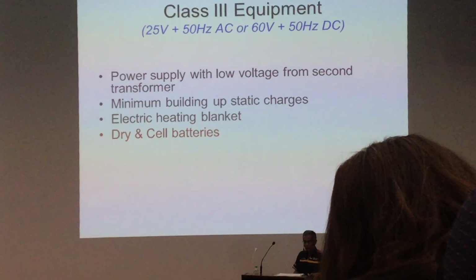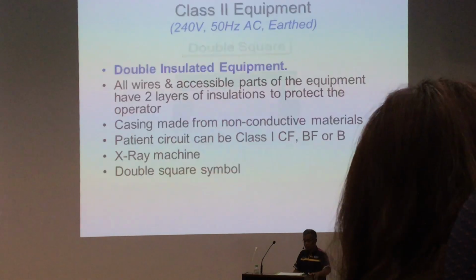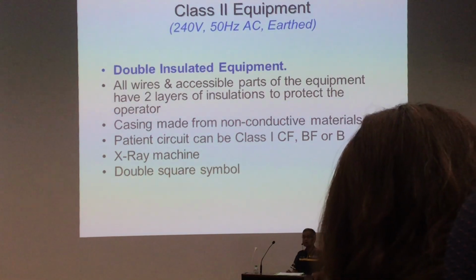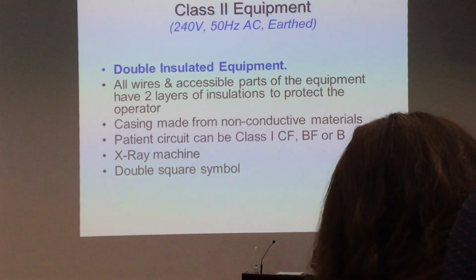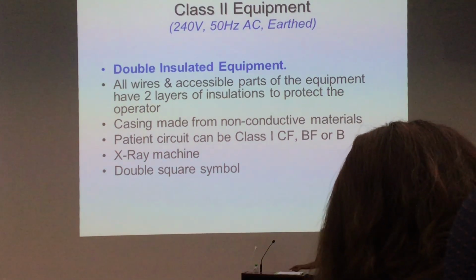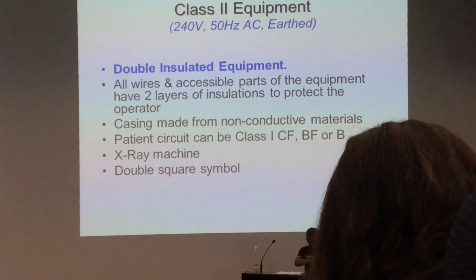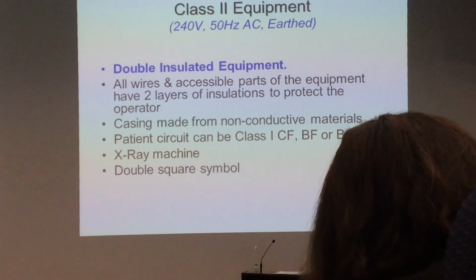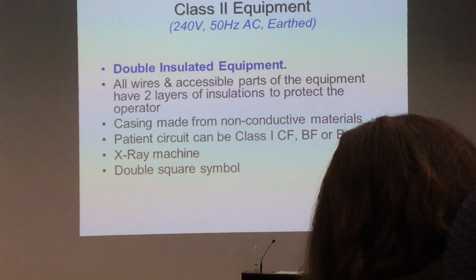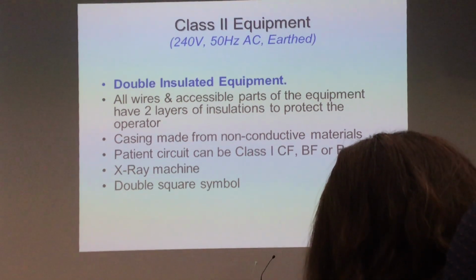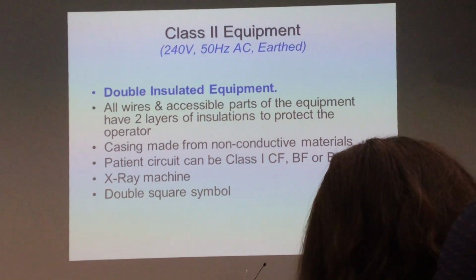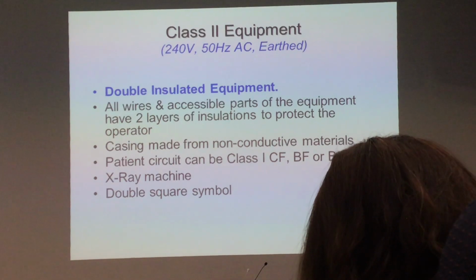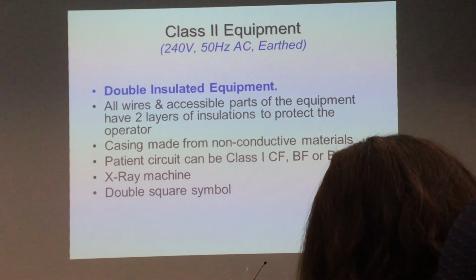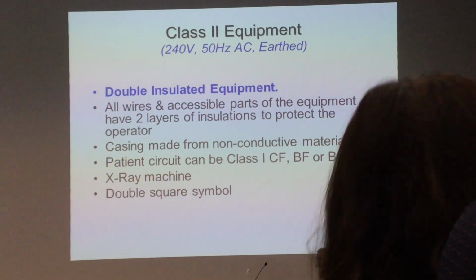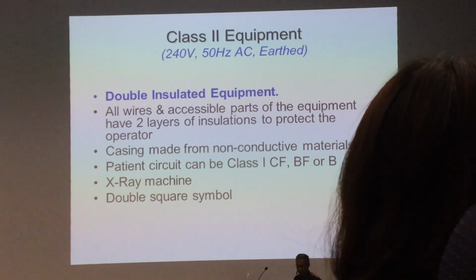So you have to provide double insulation, double layers of insulation, so that when you touch it, you are protected. Let's say the cable for X-ray, a big cable, very big, not like an ordinary cable. You step on it, you hold it, you're okay because the insulation is double. If they use one insulation, you get burned, you get electrocuted because the current is very high. So they use double layers of insulation to protect the operator, the radiographer, for example. Right?